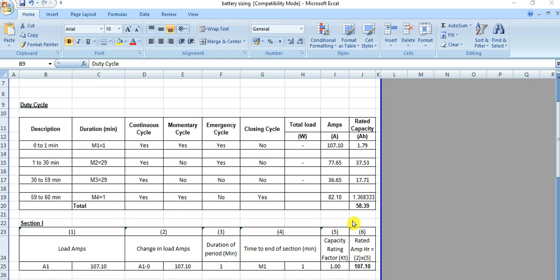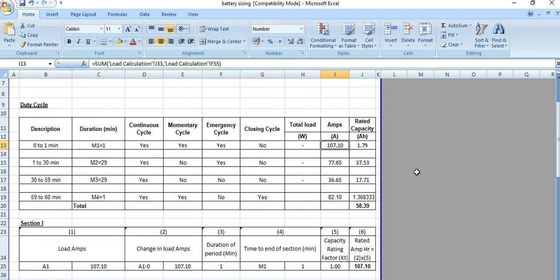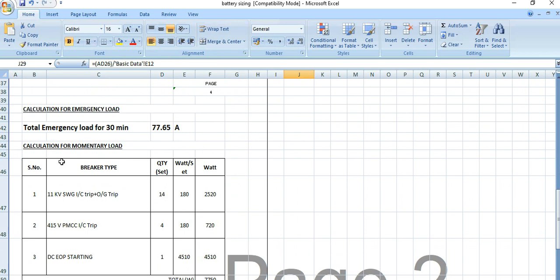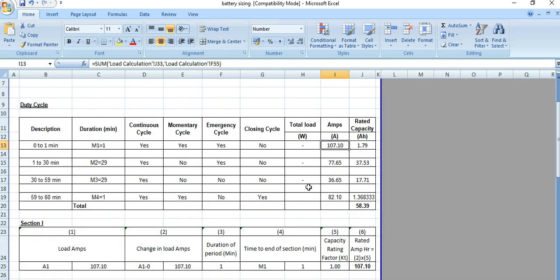This is the battery sizing calculation page. Based on the duty cycle and calculated load, we need to assign the loads. From zero to one minute there was a continuous cycle load, then momentary load, emergency load — with no closing load — coming to 107.1. So we have already calculated this load: continuous load, emergency load, momentary load, and closing load. Based on that, we need to map those load requirements here.